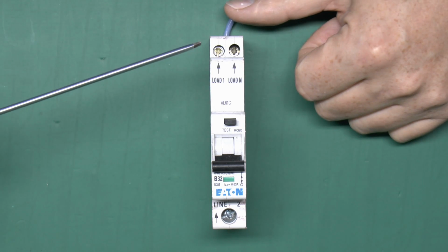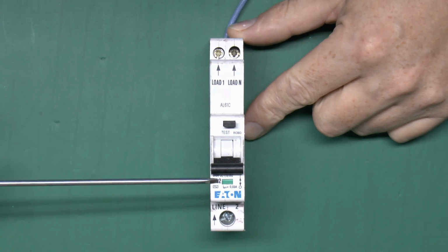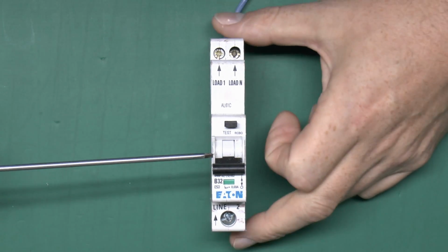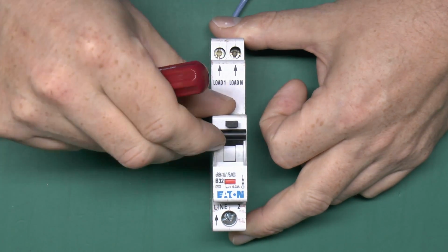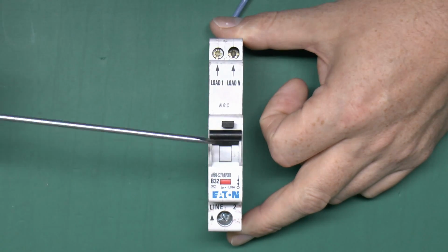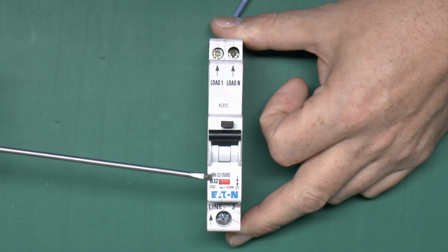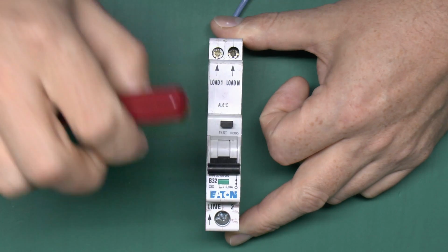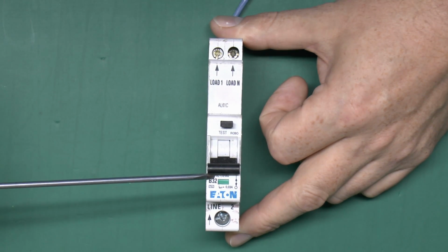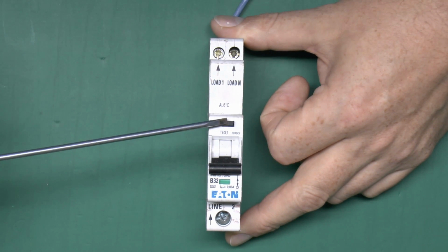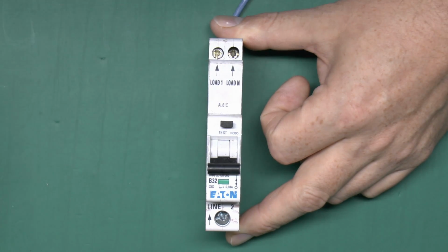Now this device is one which can react to both overloads and has the RCD functionality built in. These are generally referred to as RCBOs, and in this case it has this B32 marking here, which indicates that it is a type B 32 amp circuit breaker. And again, it's got the little test button for the RCD function as well.